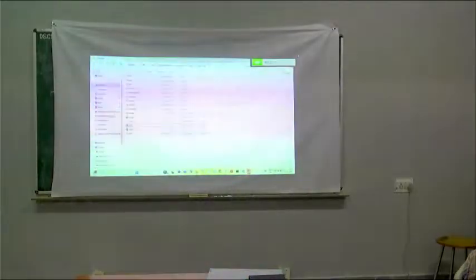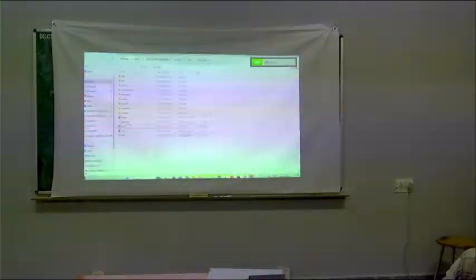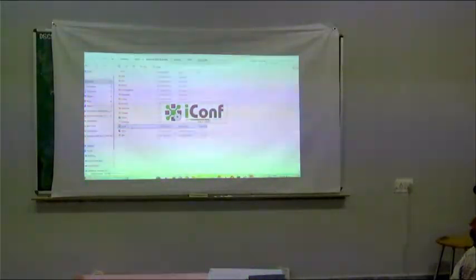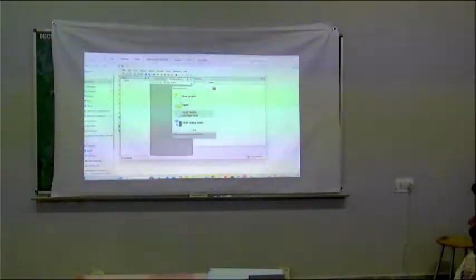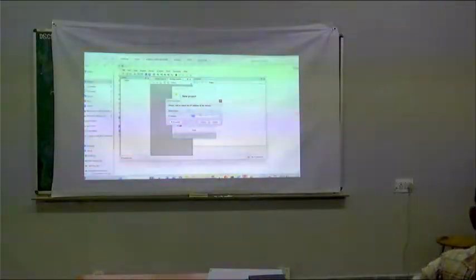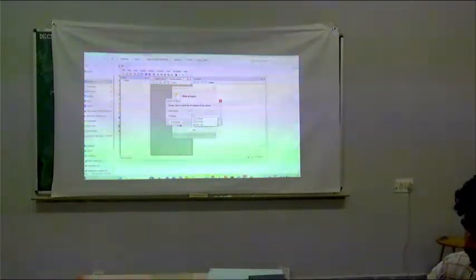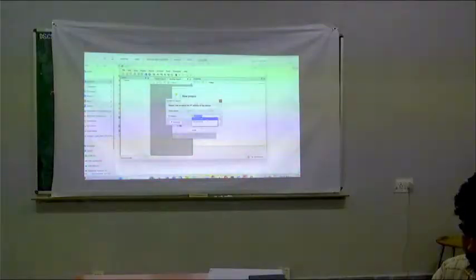And whenever I connect it in a loop as a daisy chain, I have to set different meter IDs for each of these devices, and then I have to ask the manufacturer what the mapping address of this device is. So what the manufacturer gives me is a mapping address telling that these are all the addresses on which I am sending the various data. So voltage is coming at, for example, address 101, 100, frequency on 102, like that it gives the address.